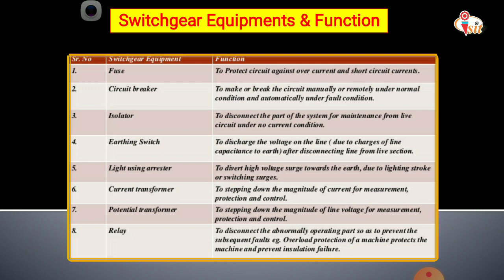The fourth equipment is the earthing switch, whose function is to discharge the voltage on the line after disconnecting the line from the live section, for maintenance purposes. The fifth is the lightning arrester, whose main function is to divert high voltage surges towards the earth due to lightning strokes or switching surges, by providing a low resistance path to ground so that fault current goes directly to ground.